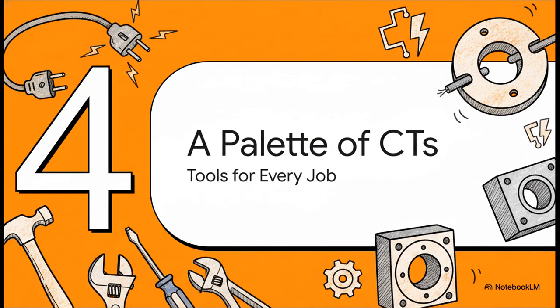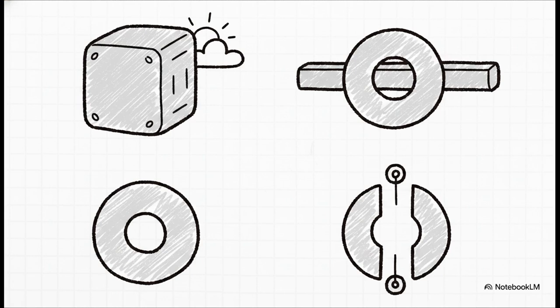Moving on to Section 4, a palette of CTs, or tools for every job. You wouldn't use a sledgehammer to drive a tiny screw, right? Same goes for CTs, there are variations built for specific environments. We've got indoor and outdoor models, which depend on their insulation, think resin casts for inside and tough porcelain or polymer for outside. Then there's the bar type, featuring a solid bar built in as the primary. You also have window or ring types, where you just slide your cables straight through the open center.